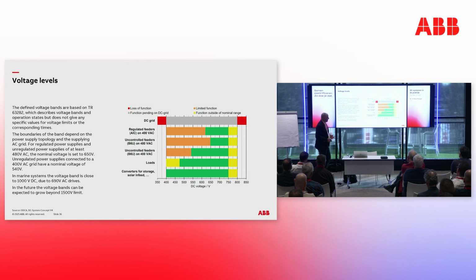Now you will probably see where I was coming from with 'DC doesn't exist,' because the converters in, for example, industrial DC grids, on the load side, are asked to operate in a 350 volt band. They have to provide full functionality in this high band. Why did they choose such a high band? Partly it's because of the power flow control, but partly it's also because of interoperability between different brands.